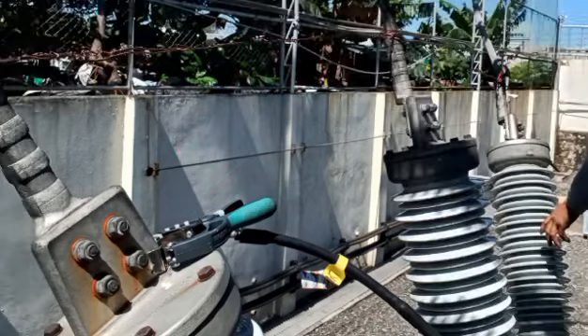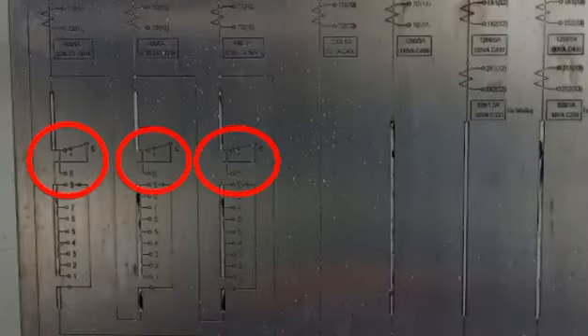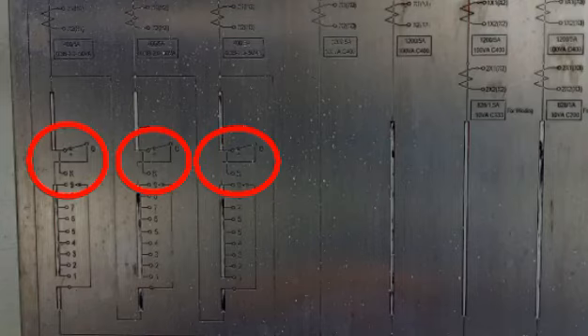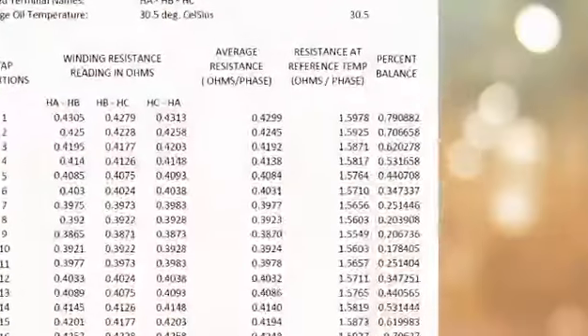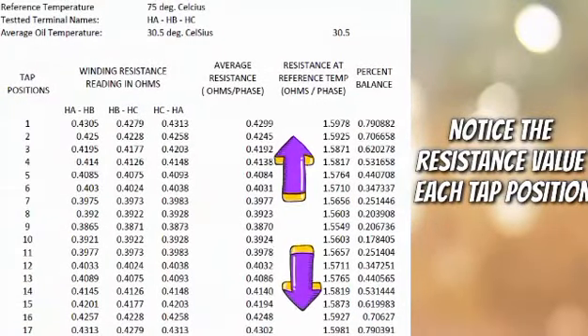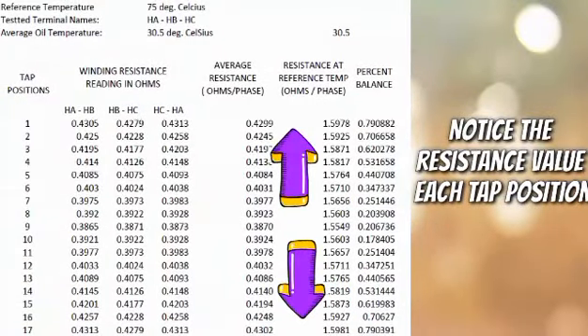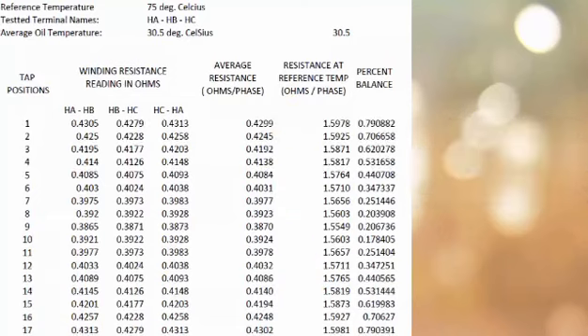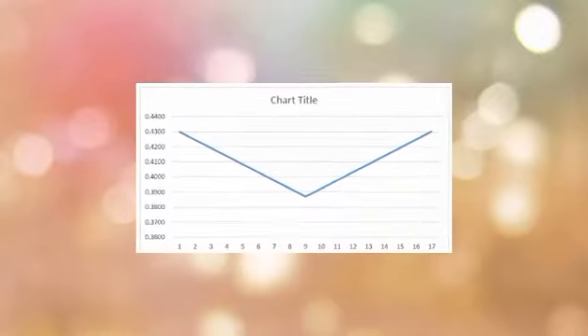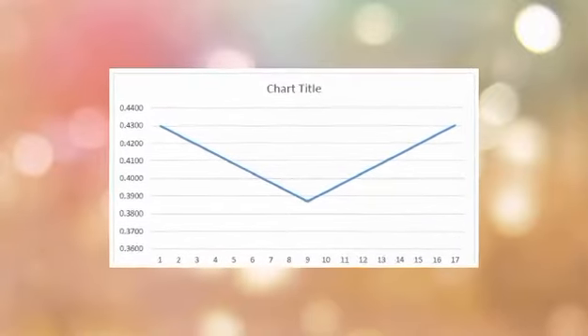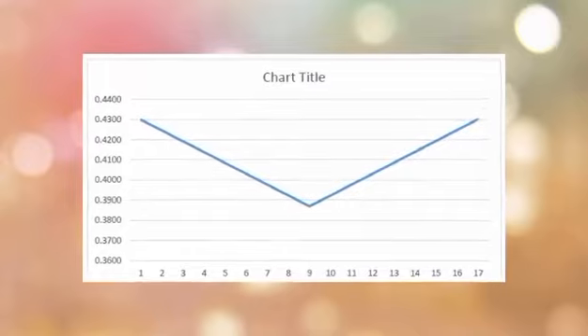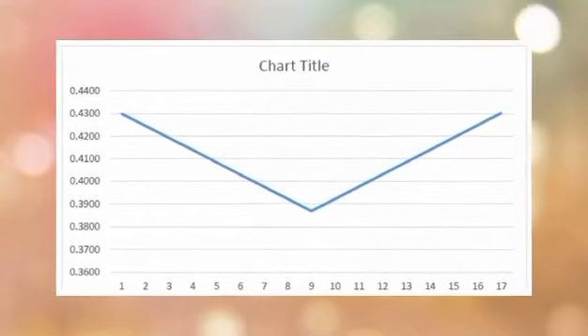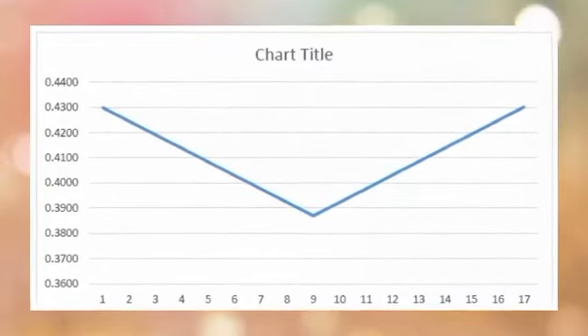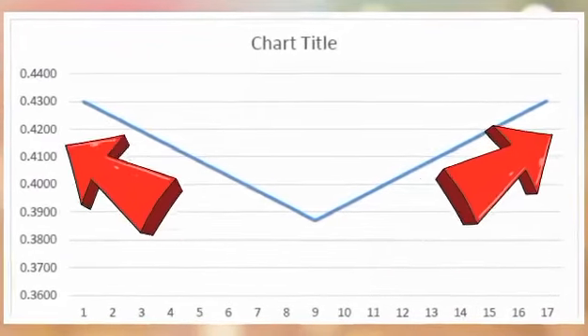Depending on the design of the OLTC, one that uses a selector switch to change the connected winding of the transformer will manifest in the graph figure. Just like in this example. Unlike the first chart, which creates a straight line up to the last tap position of the OLTC, this one has a V-type chart due to the change-over selector that diverts back to the same winding but a discrete tap. Just be reminded, this current-voltage method of measuring the winding resistance of the transformer should be repeated for each pair of line terminals of the winding at every tap position.